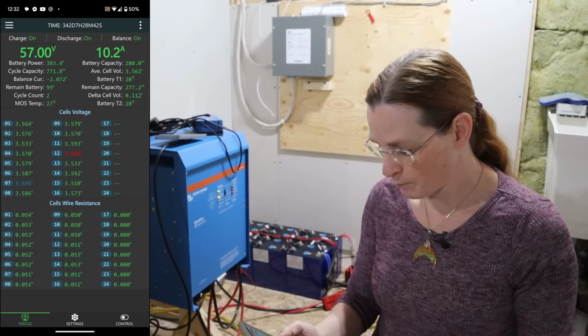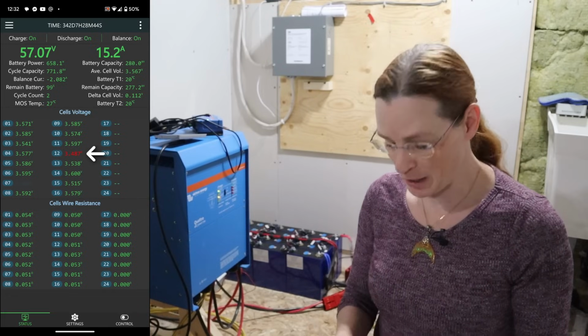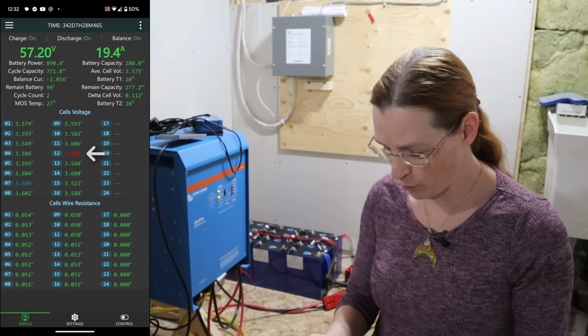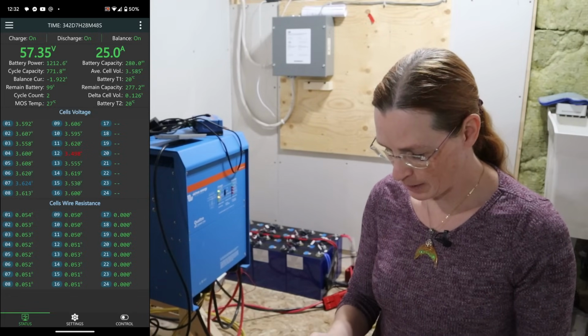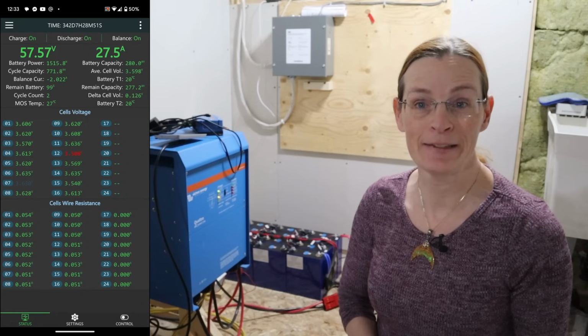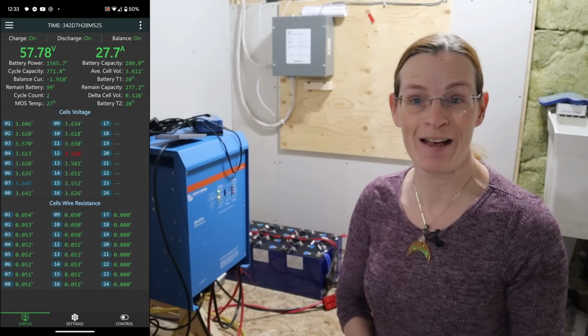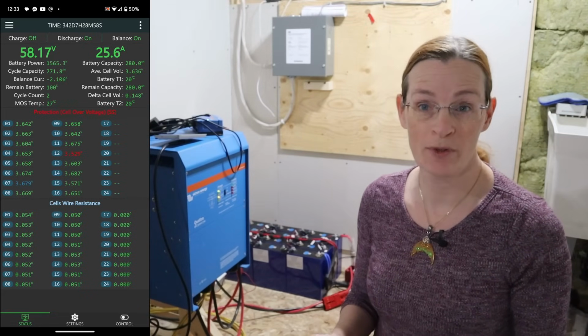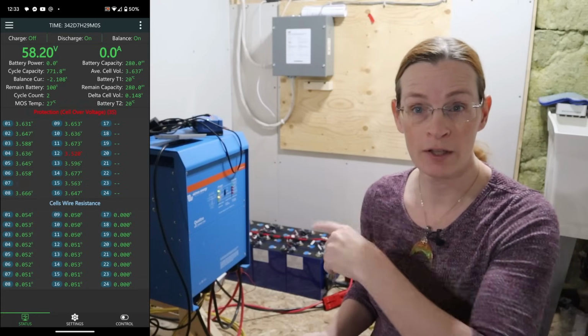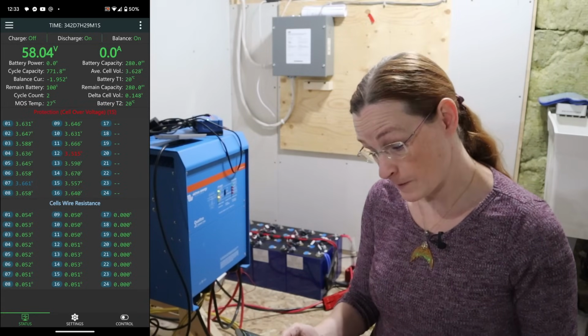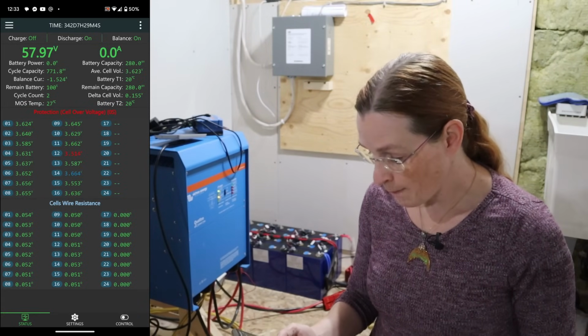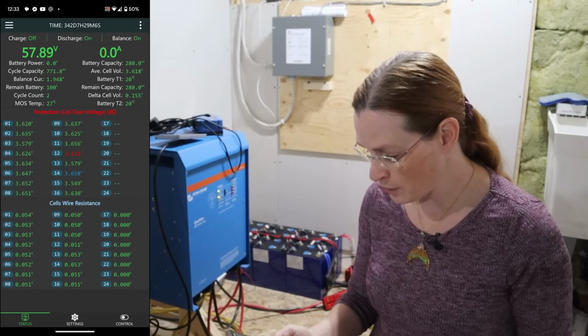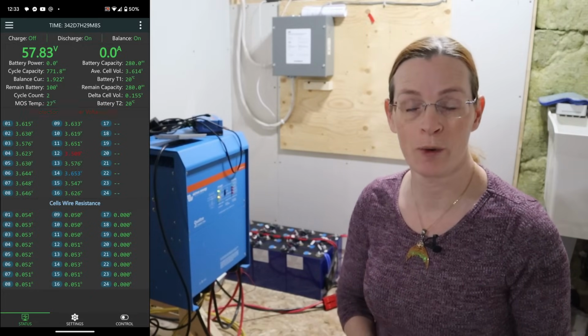But ironically it's cell 12 that's really low, I think. Yeah, 3.49. So maybe cell 12 isn't healthy after all. But it wasn't the one that stopped the discharge, it wasn't the lowest when the inverter shut off. So I don't know, but in any case it's the only one that's really low, so I'm going to let it sit here for a while and see if it'll come back up.